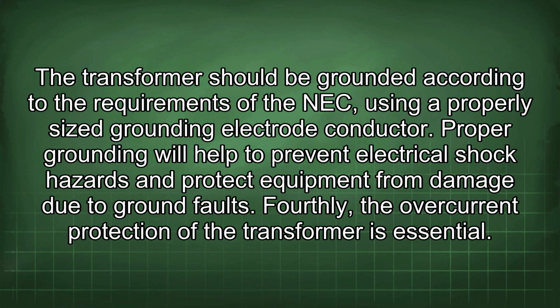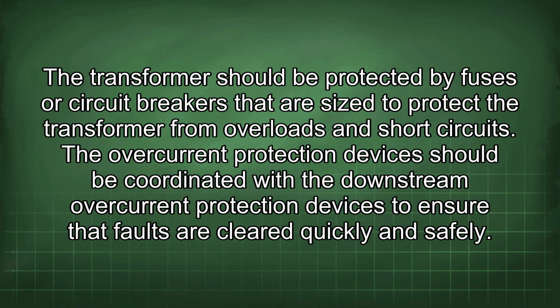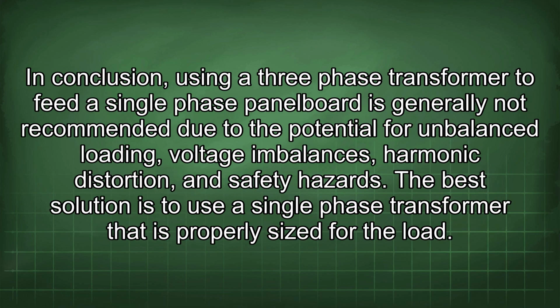Fourthly, the overcurrent protection of the transformer is essential. The transformer should be protected by fuses or circuit breakers that are sized to protect the transformer from overloads and short circuits. The overcurrent protection devices should be coordinated with the downstream overcurrent protection devices to ensure that faults are cleared quickly and safely.